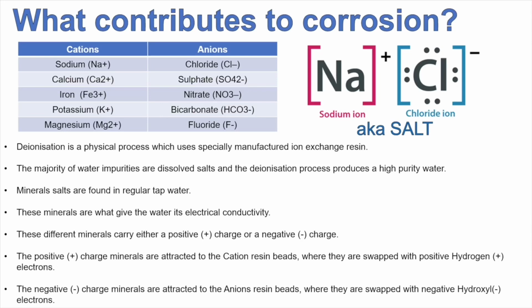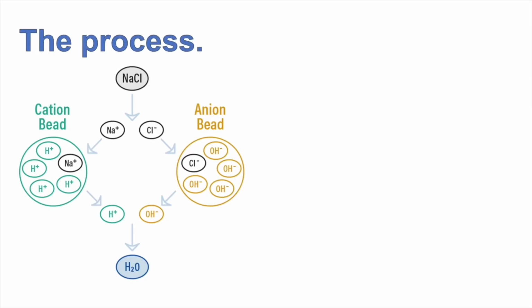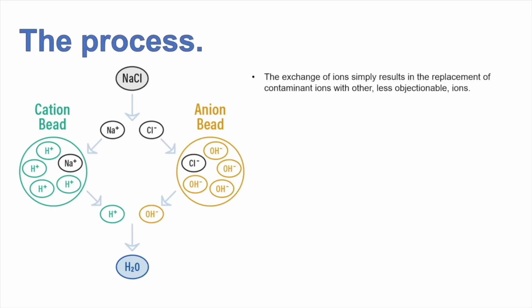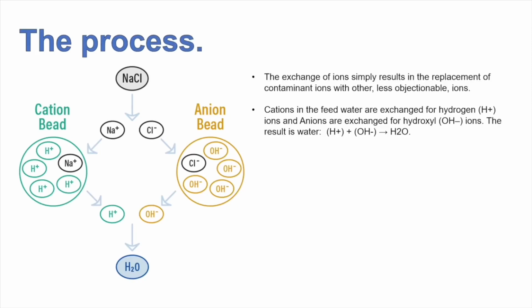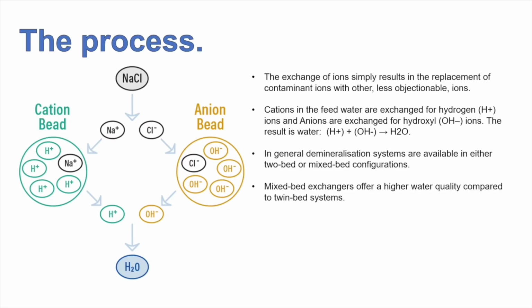The negatively charged minerals are attracted to the anion resin beads, where they are swapped with negative hydroxide ions. Right, so what we have here is the cation beads and the anion beads. We've taken sodium chloride as an example. So the sodium is positive, so it's going to get attracted to the cation bead, and the chloride is negative, so it's going to get attracted to the anion bead. They swap places, and essentially what we're going to get is pure H2O.